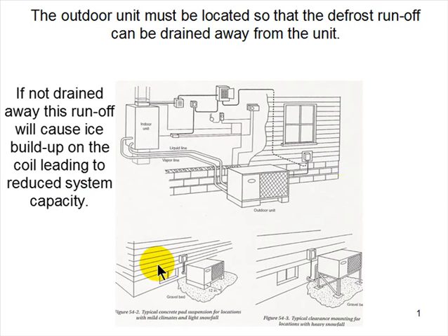If not drained away, the runoff will cause a buildup of ice on the bottom part of the coil and reduce system capacity. All right, when ice is there, you don't get any heat transfer. So your capacity is going to go in the dumper. So it should be elevated, even in warm climates. And I'm not talking about southern Florida. I mean in warmer climates where the winter is not so severe.